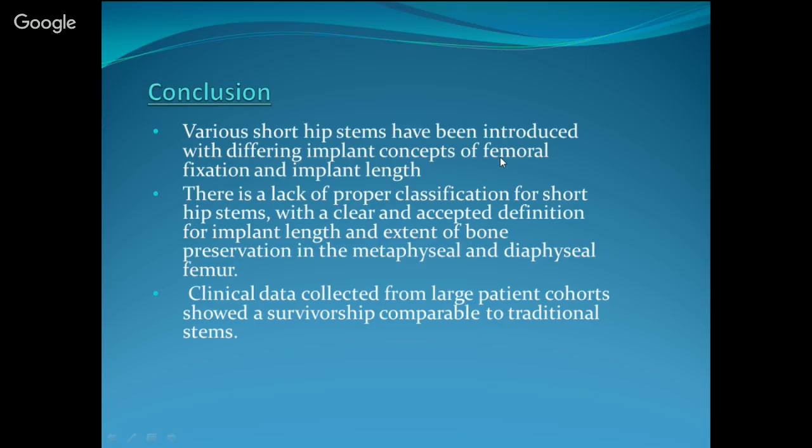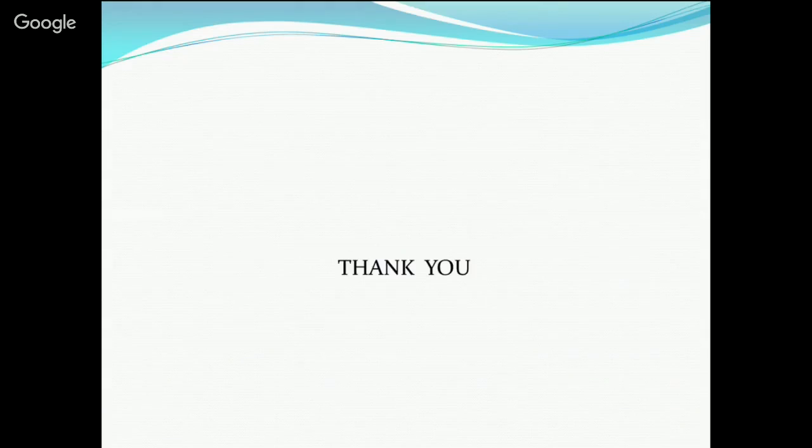So the conclusion is that various short stems have been introduced with different implant concepts of femoral fixation and implant design. There is a lack of proper classification for short hip stems with a clear and accepted definition for implant length and extent of bone preservation, metaphyseal and diaphyseal. Clinical data collected from a large patient cohort showed survivorship comparable to traditional stems within the 5-year period. So this is all about the new implant we have.